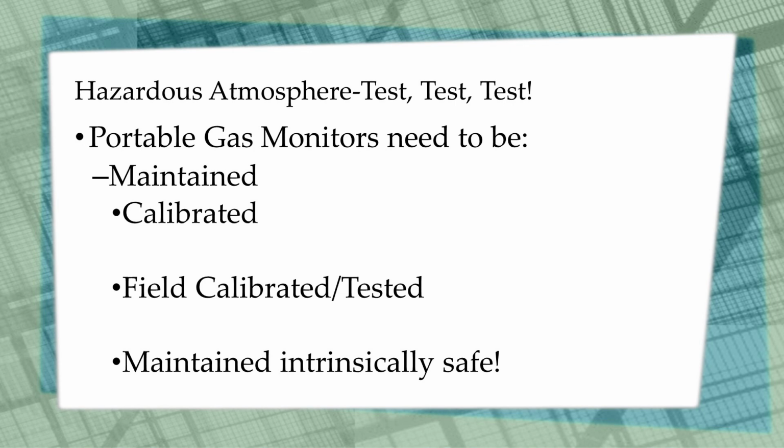Sometimes they send sensors or cells, and the cells are already calibrated, and you replace the old cells. Sometimes, if you're certified, you can do the calibration yourself, or locally someone might be trained and certified to do the calibration correctly. And typically it's at intervals of yearly, every 3 years or something like that. What matters is that you do it as often as the manufacturer requires. I also encourage people to do field calibration and testing.